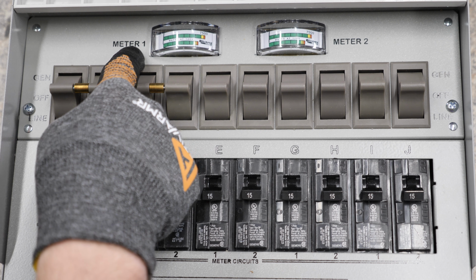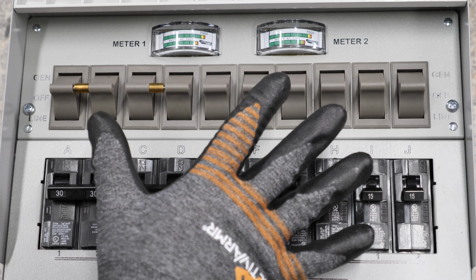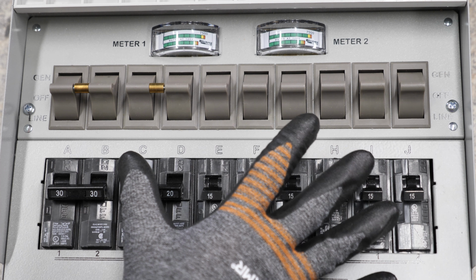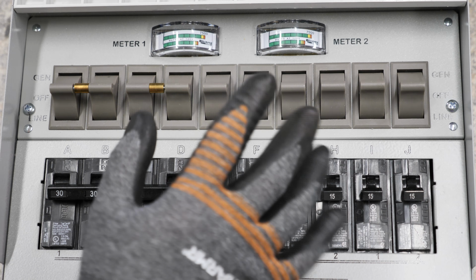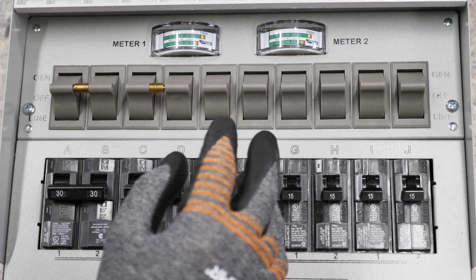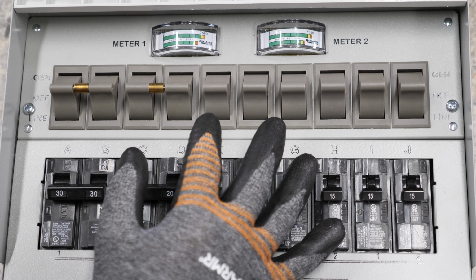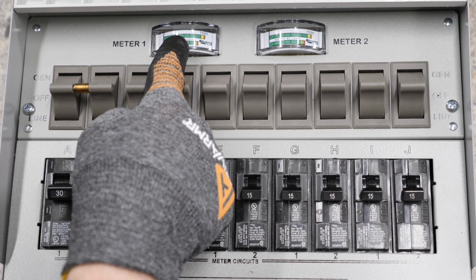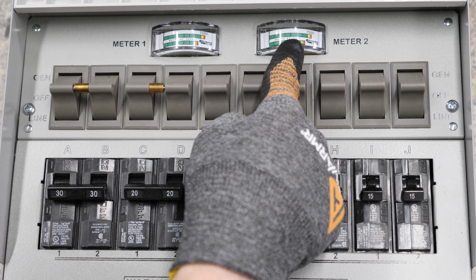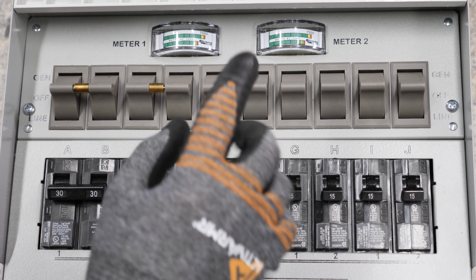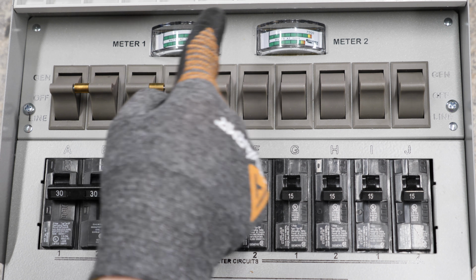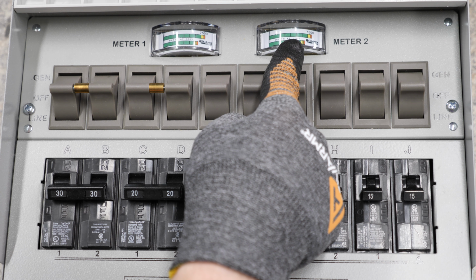This is basically L1 and L2 from battery backup. Since this is a 240 volt panel, if you're not aware, there are 2 120 volt lines — that's how you get 240 volts. So this is one 120 volt, and this is the other 120 volt. Whenever we're in backup mode, this is going to show you how many watts are running on each leg.